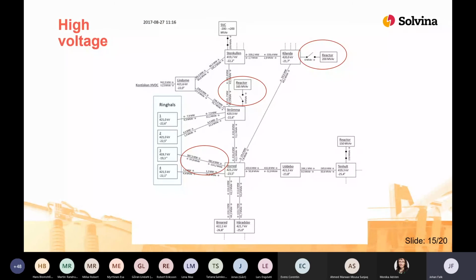So the first visualization I want to show you is for this instance. The main focus for the visualization is to look at reactor control and reactive power exchange between the grid and Ringhals. And I will only talk about some few key points for each occasion. You can read more in the report if you want. So here we can see a situation with high voltage levels in the entire region. In the data, we could see that the voltage was high for a long time prior and after this instance. And we can see that the reactors at Strömma and Kilanda are disconnected, and that these high voltage levels result in Ringhals block or unit 3 having to absorb quite a high value of reactive power.